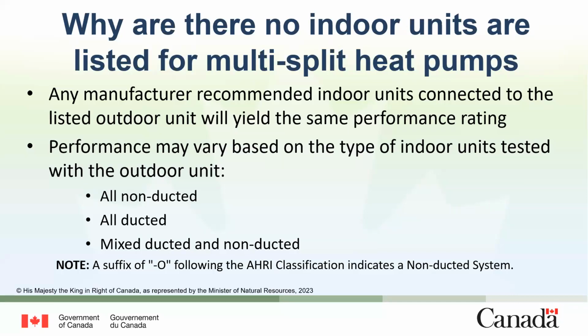So the first combination will most likely show when they were tested with all non-ducted indoor units. The second, when the outdoor unit was tested with all ducted indoor units. And the last one, when the outdoor unit was tested with mixed ducted and non-ducted. And just as a tip, if you look at the AHRI classification and you see a -O at the end, that's an indication that the indoor units connected to the outdoor unit are all non-ducted.